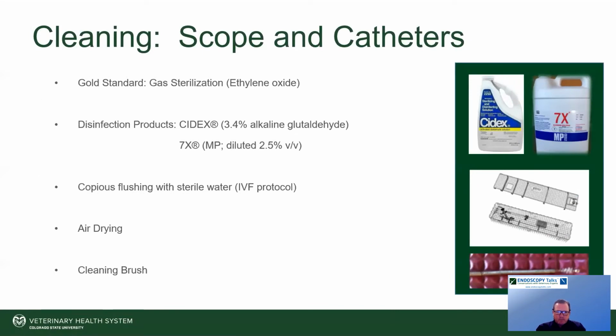So cleaning the scope is really important. Gold standard would be sterilizing it. It can be gas sterilized. It can also be steam sterilized. I believe when we talked to the manufacturer of the scope, they said potentially repeated steam sterilizing would shorten the lifespan of the scope. There is a cage that the scope can go into and be wrapped and then sterilized, so a protective cage for the scope. Chemical sterilization with different products can be used following cleaning, the brushes, etc., and then air drying like any scope you would use. So cleaning and sterilizing in between use is important.